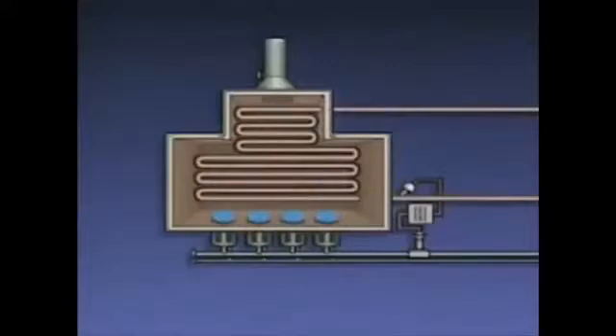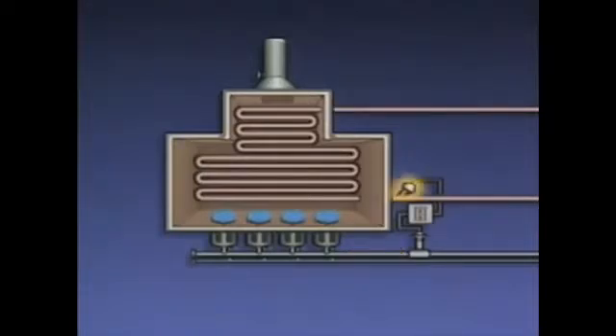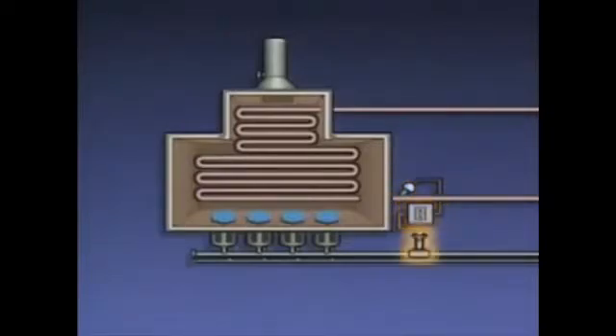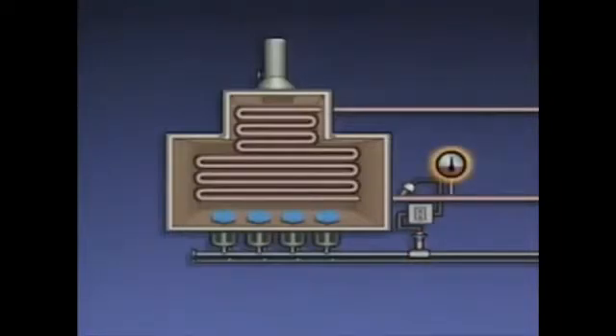You should know how your furnace's control systems work, so you can monitor the way they're controlling the furnace. Let's look at a typical example. This system controls the process fluid outlet temperature by adjusting fuel flow to the burners. There's a thermocouple to measure the outlet temperature, a temperature controller, and a fuel flow control valve. During operation, there's a desired outlet temperature, or set point.